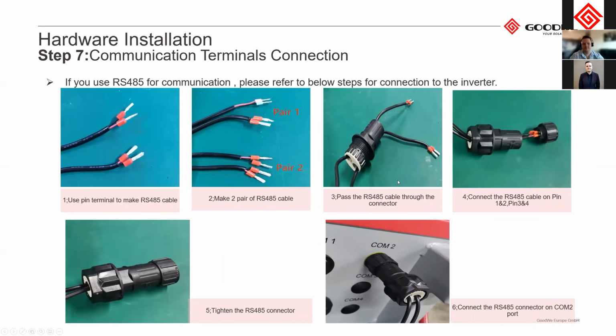Now we come through to the RS485 communication connection. So on the inverter, we have this terminal plug for the IP rating. As you'll see, we do include ferrules for the ends. So it's important to push your cable through the connectors, then make your cables off. So as you'll see on this one, we're using 2 pairs. So that's an in and an out. So if we're daisy chaining multiple inverters, we use 2 pairs. So that will go from one inverter to the next inverter. And then lastly, it will then go to our SEC1000.